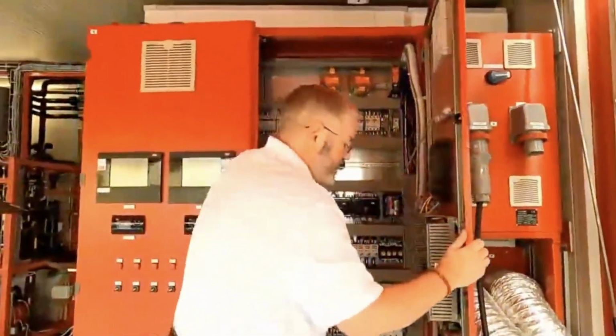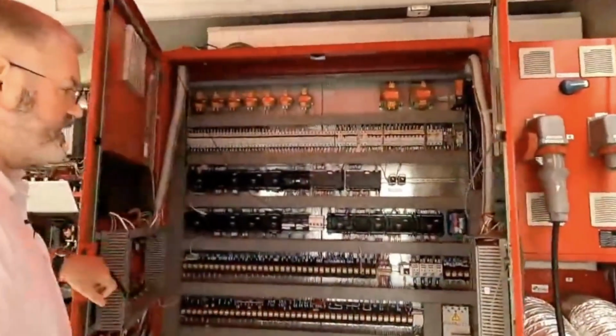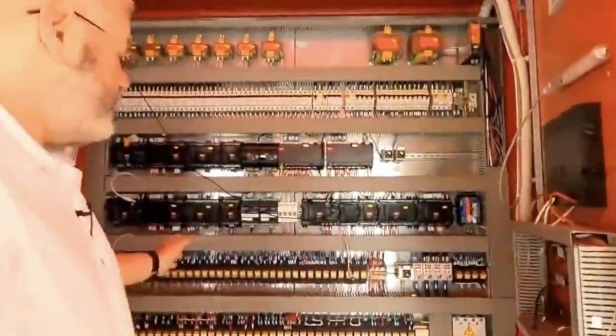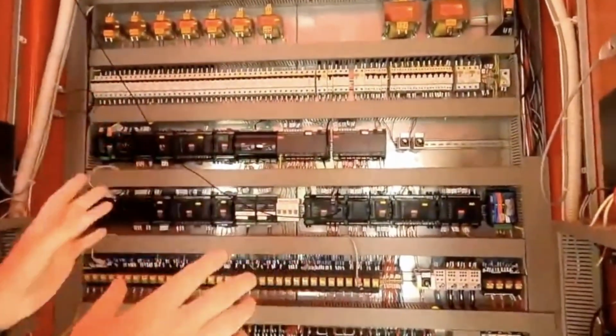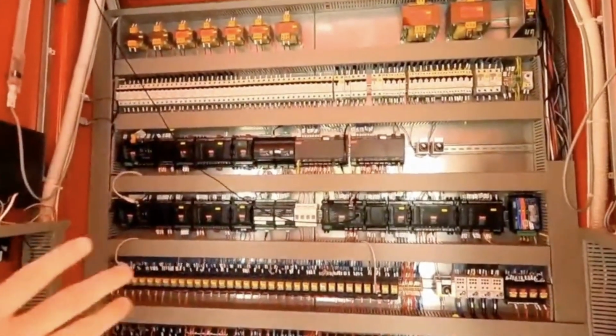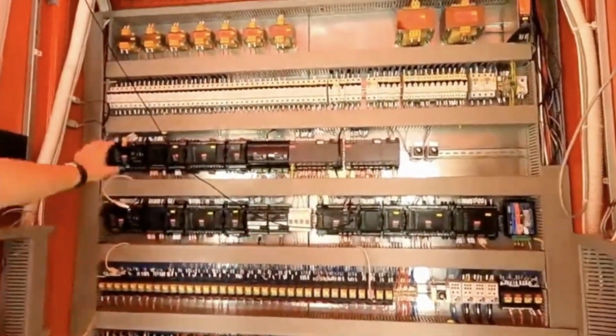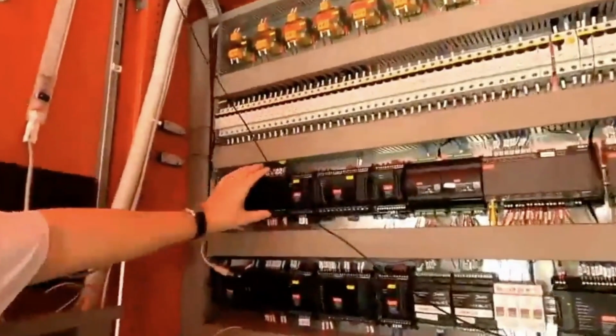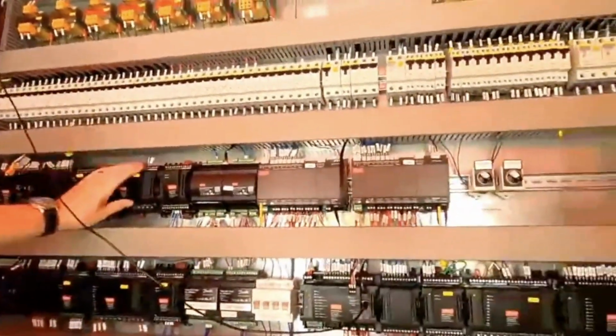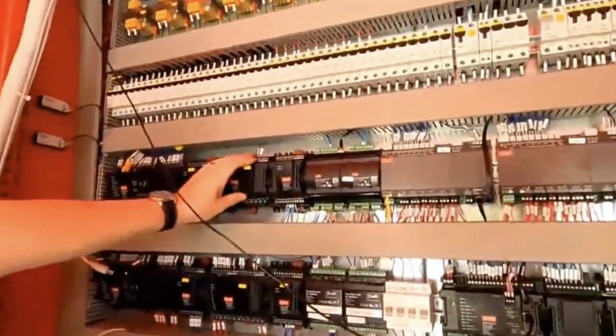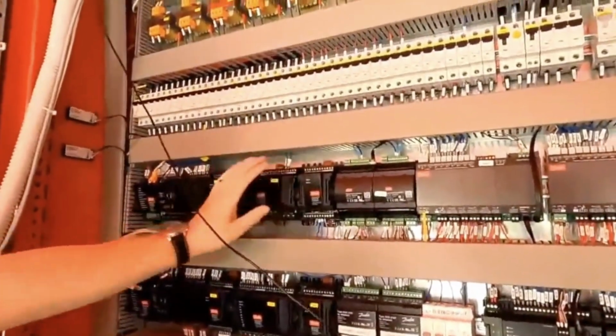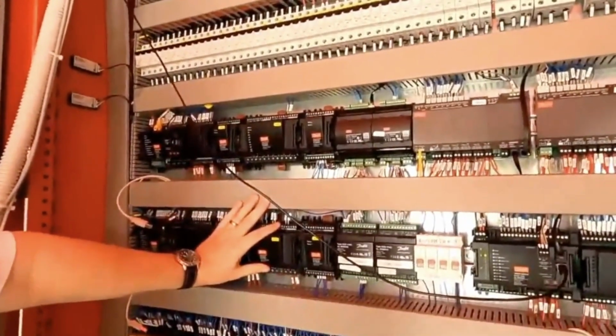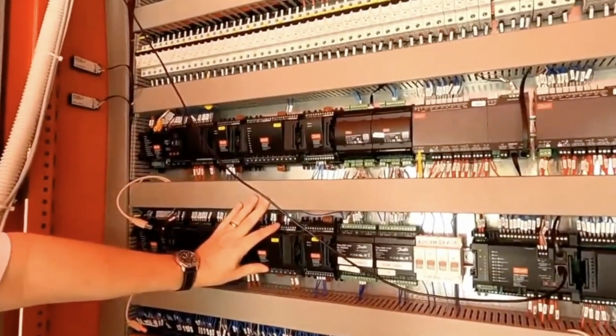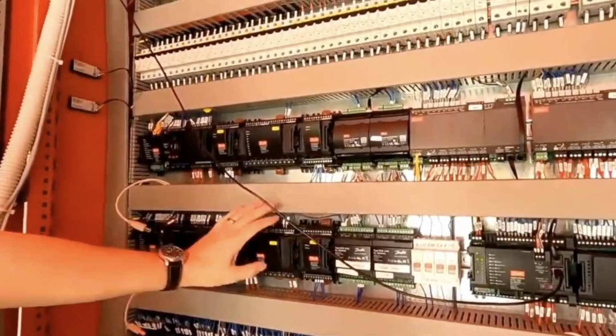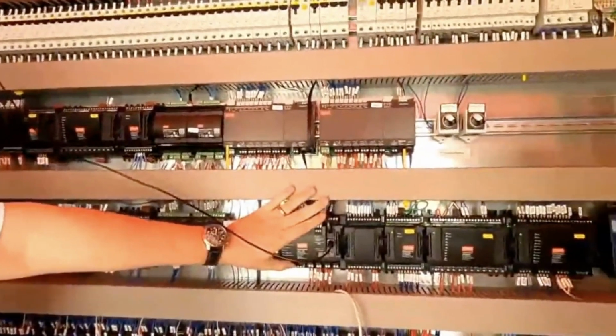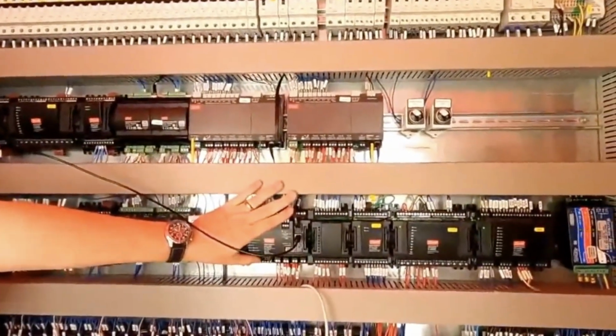If we move from there, inside our control panel here, we actually have 3 modes of operation. I want to make the point that all the components you see here aren't what's necessary for a small medium temp transcritical CO2 system. It's just this top row, and then we have it 3 times. So the top row operates just medium temp transcritical. We flip a selector switch. This will power down, and then the one below it powers up, and that's medium temp transcritical with parallel compression.